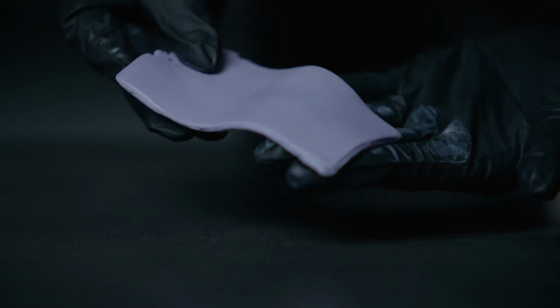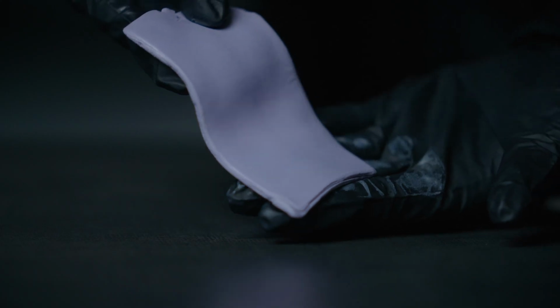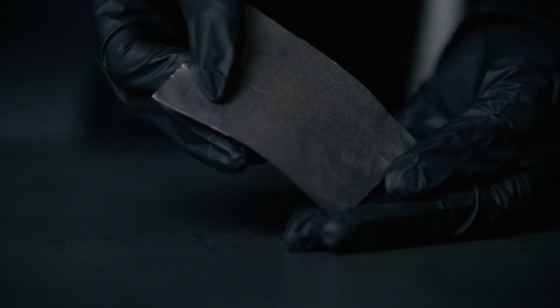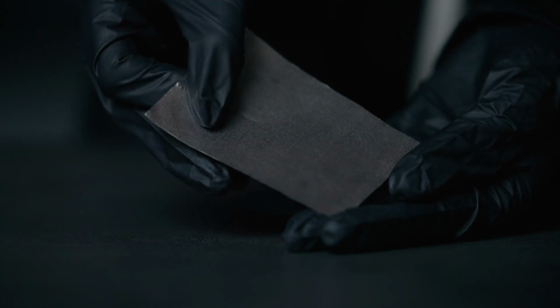Through plane measurements tell us how heat moves across the thickness of a sample. They're ideal for testing thermal interface materials, packing materials, and multi-layer composites where vertical transfer is critical. In-plane measurements, on the other hand, show how heat spreads across the surface. This is vital when evaluating films, coatings, graphene composites, or heat-spreading layers in electronics.